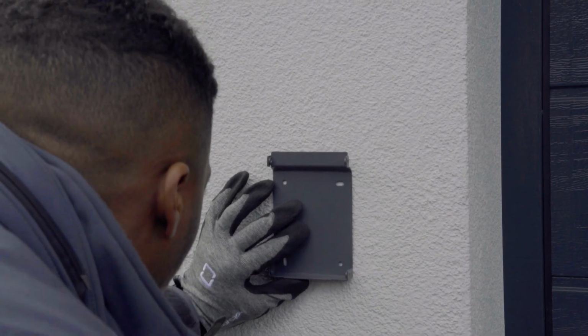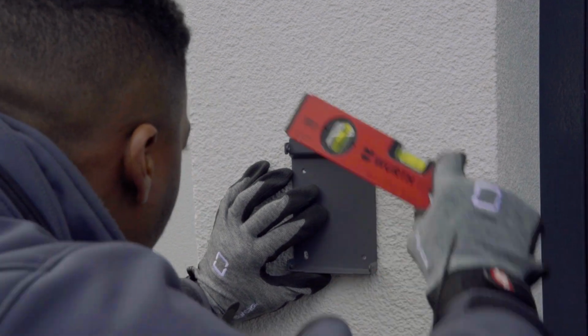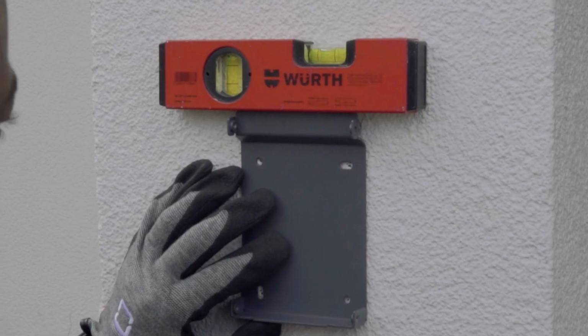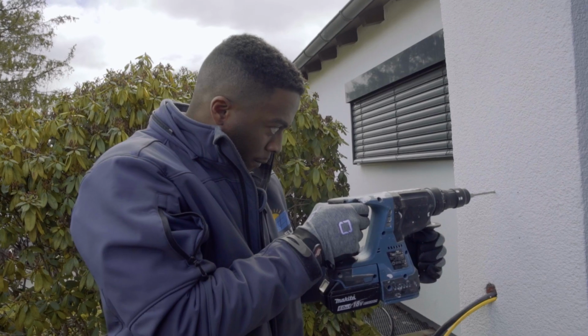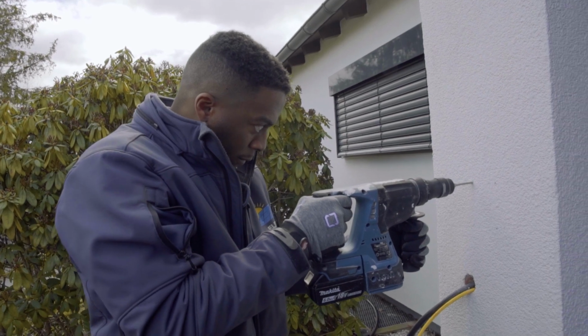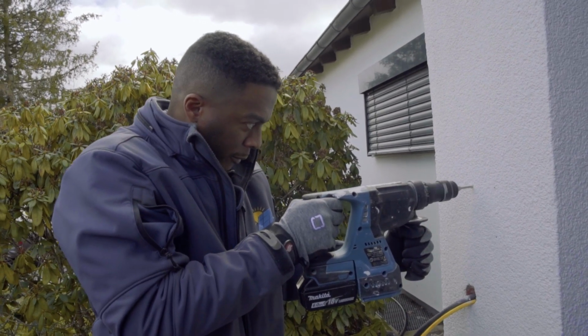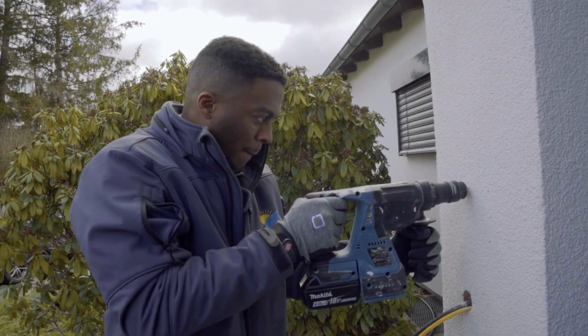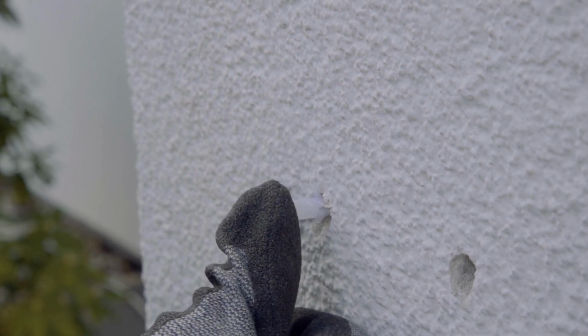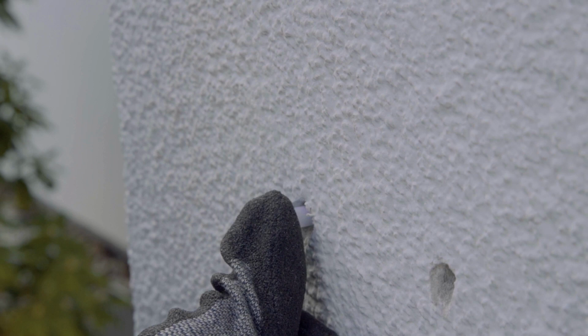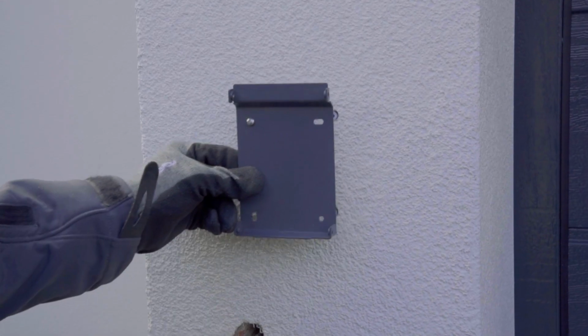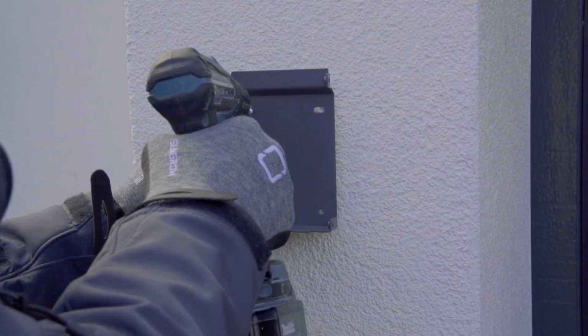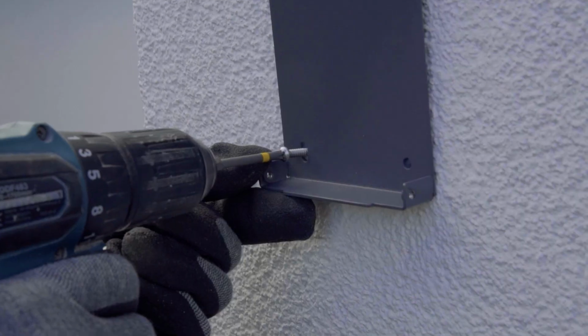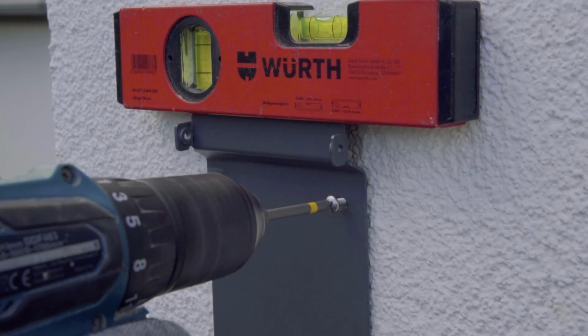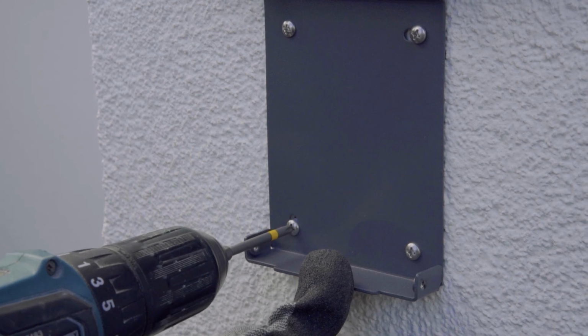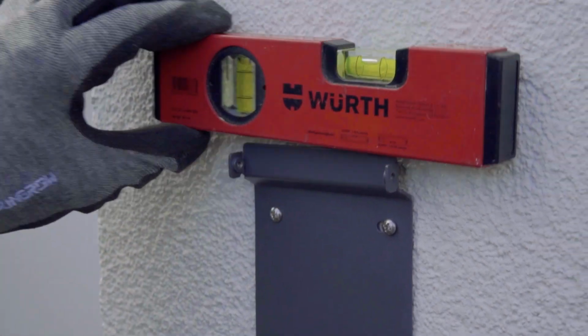Use a spirit level to make sure the position of the backplate is horizontally aligned and mark the drill holes with a pen. Using a 6 mm bit, drill a 45 mm deep hole into the wall markings and insert the plugs into the holes. The screws and plugs for mounting the backplate are included in the delivery. Place the backplate on the wall and tighten the screws with a screwdriver to secure the backplate. And off we go! Let's start with the bracket installation on the AC charger.